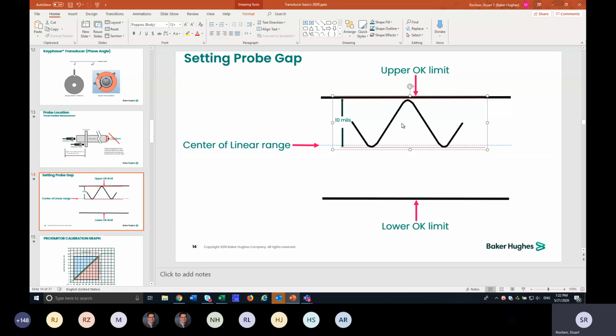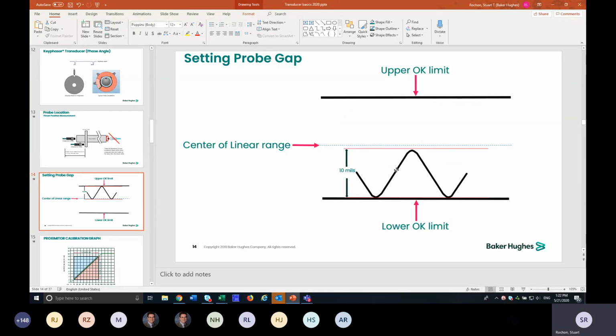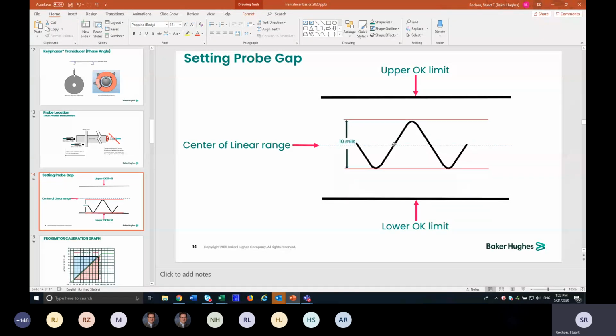So here, if my OK limit is at negative 1.6, and we only have a 1 volt difference to the center line, as long as I'm over negative 2.6, I'm not going to get into that limit. So you can have a very wide range of gap setting and not run into issue. However, we do recommend that you set it in the middle of the range to give you the greatest amount of clearance and available room possible.